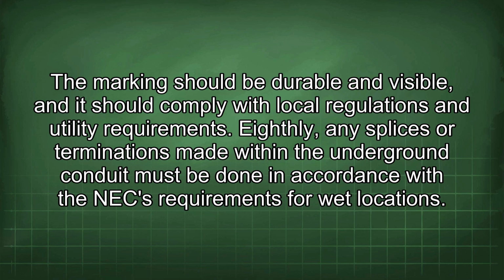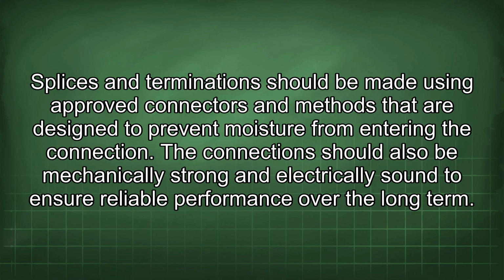Eighthly, any splices or terminations made within the underground conduit must be done in accordance with the NEC requirements for wet locations. Splices and terminations should be made using approved connectors and methods that are designed to prevent moisture from entering the connection. The connection should also be mechanically strong and electrically sound to ensure reliable performance over the long term.